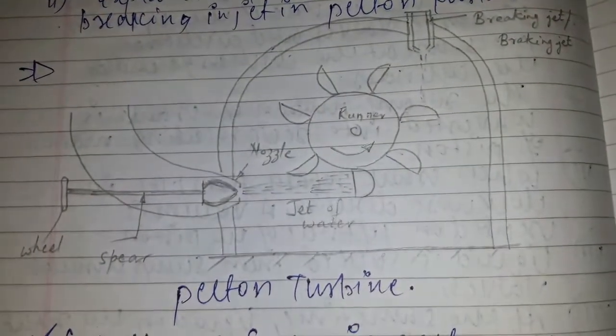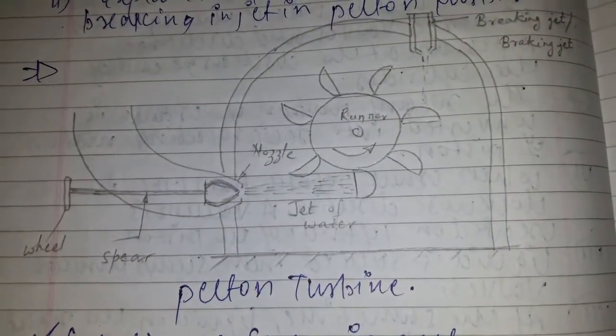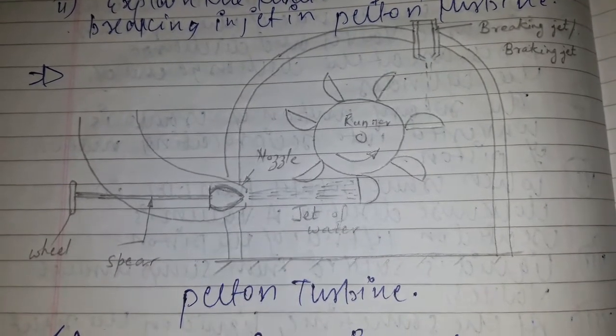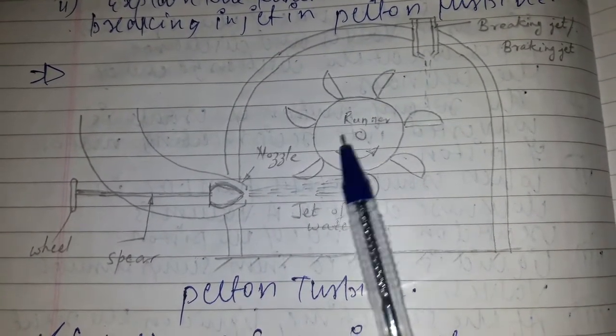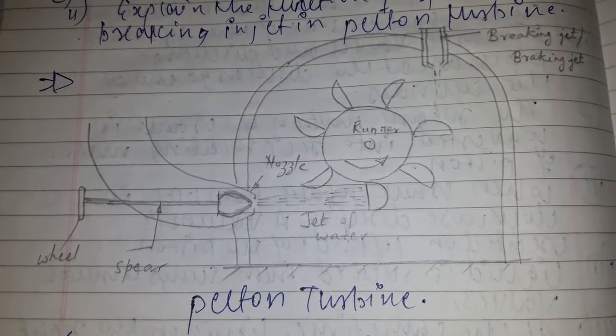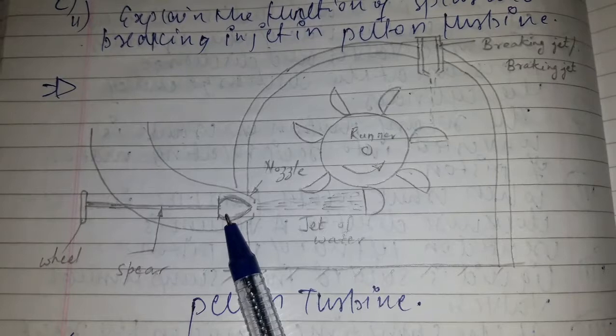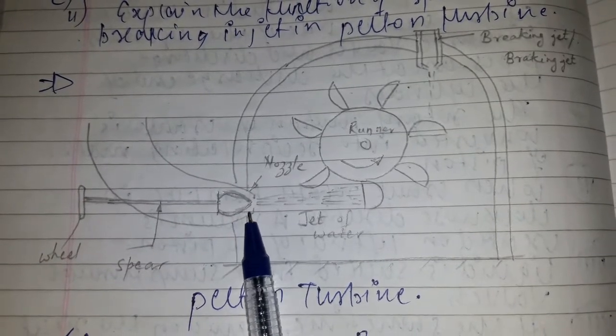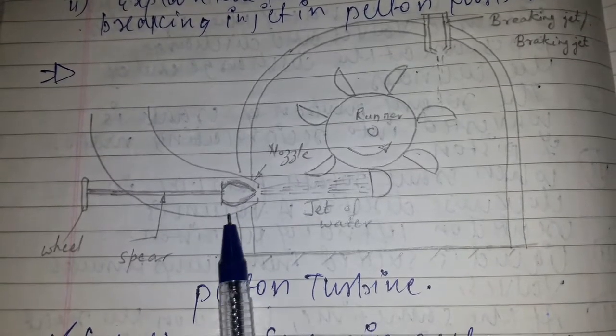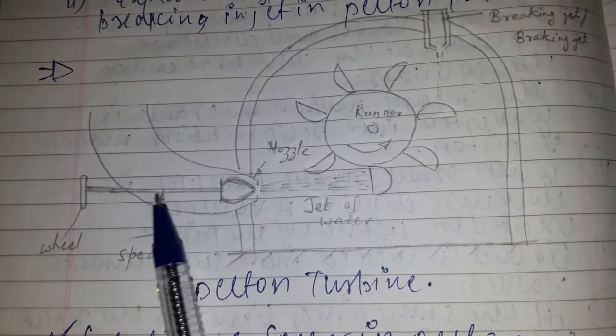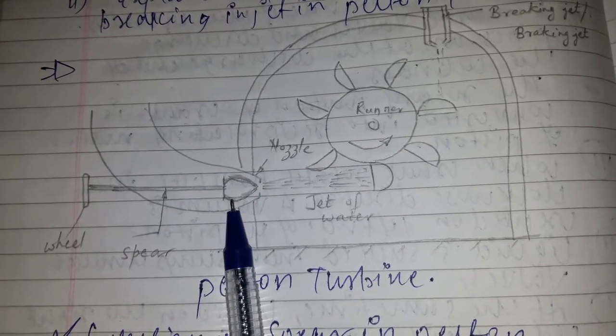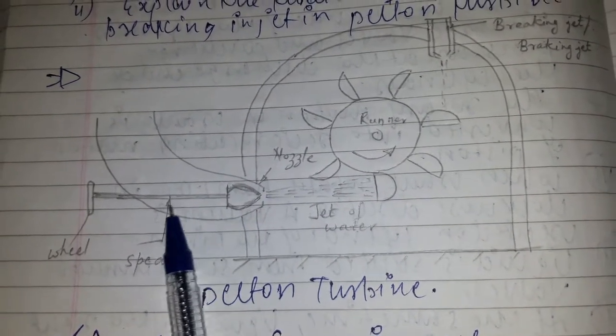Today's topic of discussion is the Pelton turbine. We will discuss the function of the spear in the Pelton turbine and the braking jet. The needle spear is provided in the nozzle to regulate the water flow through the nozzle. It provides smooth flow of water with negligible loss of energy.